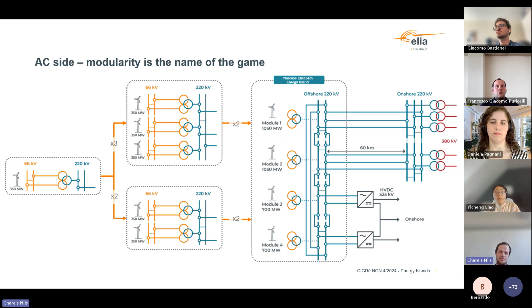Here you can see an artist impression of what we're trying to build. We can see the 2 orange boxes. The bigger one is the 1050 megawatt module housing the 66 kV GISs and the 220 kV GIS. The 700 megawatt module is the same, but only with 2 66 kV GISs. In between, we can see the power transformers, with again the benefit that these are now outside of the modules. So from a fire risk point of view, this is also good for resilience, because in case of transformer fires, we don't lose the full module. And this too we have at the far end of the island as well.